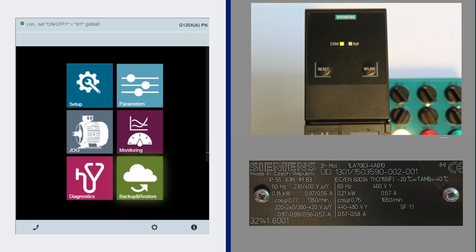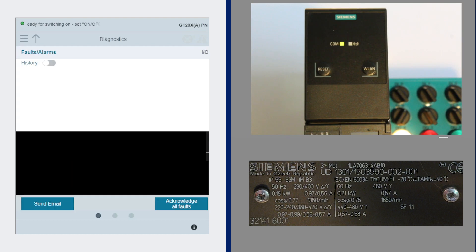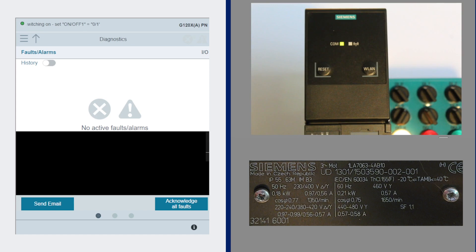There's also monitoring in the drive, which shows the set points and frequencies, the DC bus volts. You can do backup and restore. You can do simple cloning. There's also diagnostics, which is looking at the faults and warnings history. Currently I have no faults and alarms and no history because we just did a commissioning of the drive.